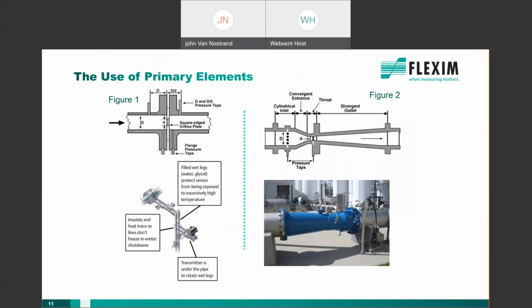Figure 1 is an orifice plate, and this is the most simplistic and least expensive type of primary element. The orifice plate is used less often due to the fact that it has a large pressure drop that's needed to measure. Flow nozzles and venturis are in the same category, and they're all governed by ASME MFC 3M. So figure 2 is more common in the water market. It's a venturi tube and it has less pressure drop, but it's very expensive and it's custom made for the application. This picture in the lower right illustrates a 36-inch venturi.